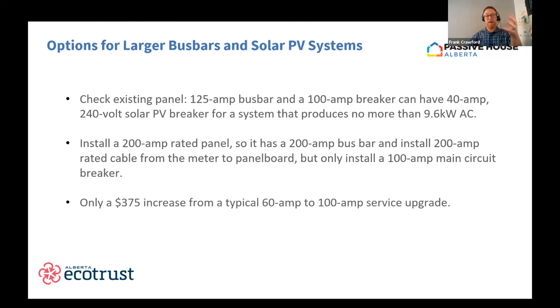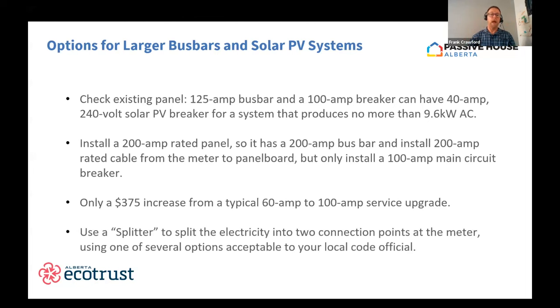The other, and this upgrade to a 200 amp panel from just a typical 60 to 100 amp panel is only about $375. So if you're upgrading anyways, or if you're building new, just put in that 200 amp rated panel with a 100 amp breaker. The other way, if your panel is far away from your meter, you can also use equipment that is called a splitter to split the electricity at the meter base into two feeds, one that feeds your solar PV system and one that feeds your panel.